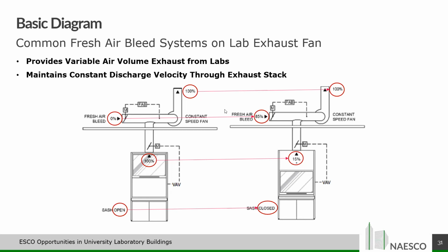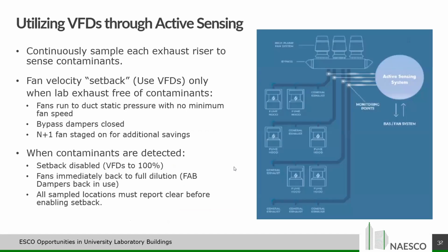So you don't have to heat or cool this. So you get a tremendous amount of savings of not having to heat or cool or dehumidify 85% of the air, but you're not getting any energy savings from this fan because there's no VFD on it. You're controlling this to maintain a constant static pressure in the exhaust plenum. So a fresh air bleed controller controls this, but great for saving heating and cooling energy, not so much for fan energy.